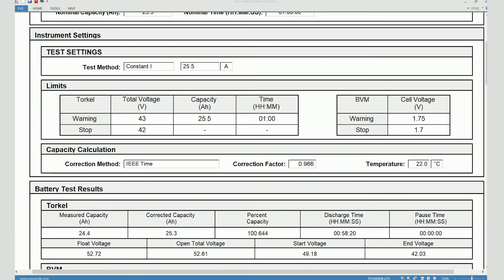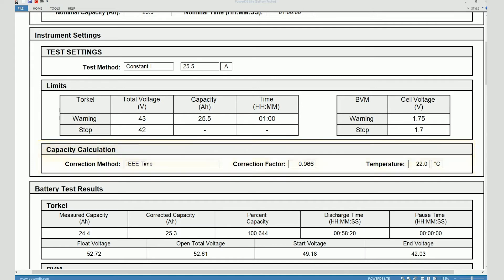Then the capacity calculation method. In this case we can see that the time adjustment method was used. You can see the correction factor which is 0.966 here based on the test temperature of 22 celsius.